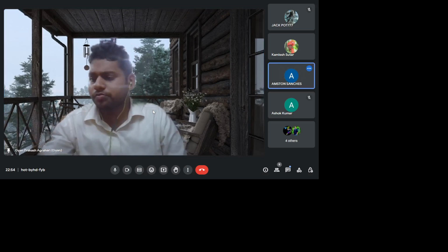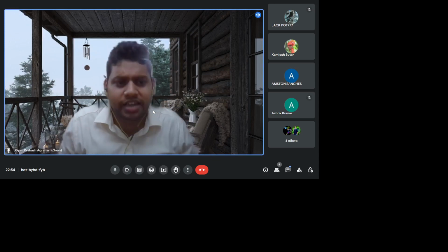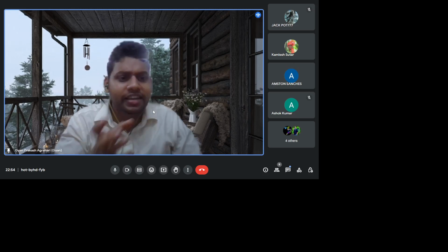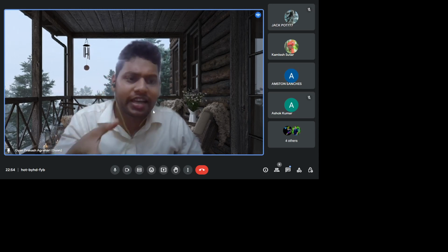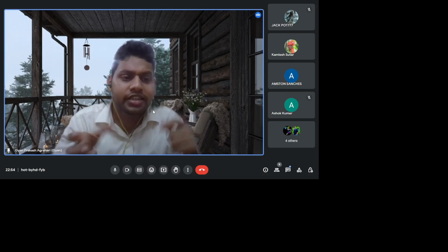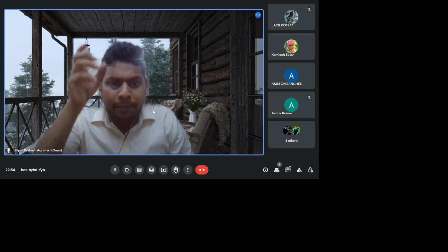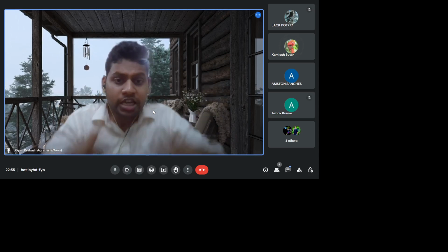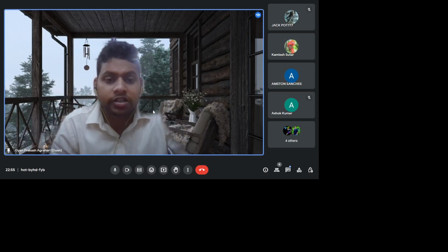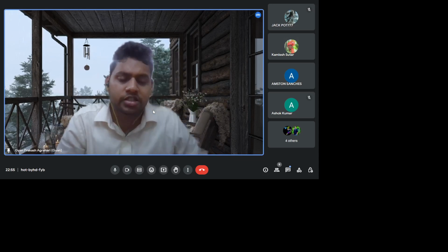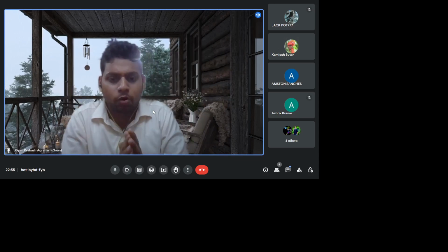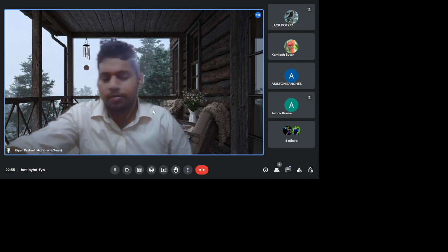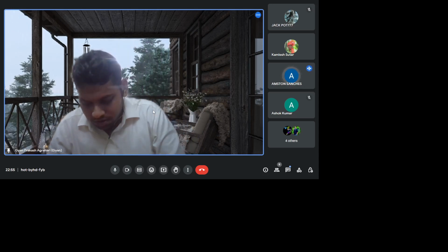And the volume of that drum is constant. That can be called Gay-Lussac's law applying, because in Gay-Lussac's law volume is constant, and when temperature decreases, pressure also decreases. Steam is getting condensed into water droplets, temperature is decreasing, pressure is also decreasing from the atmospheric pressure, so implosion can happen. Got it, guys? Okay, making sense.